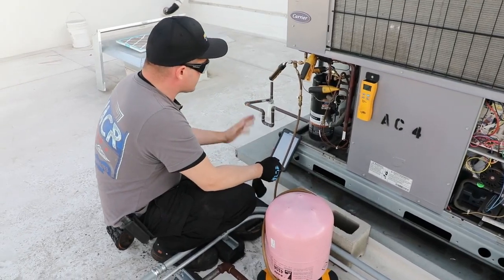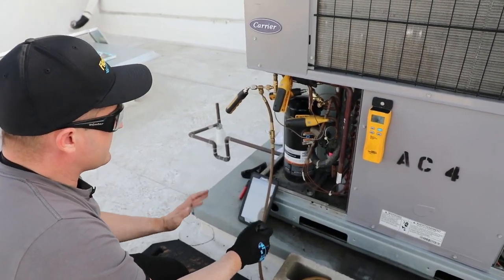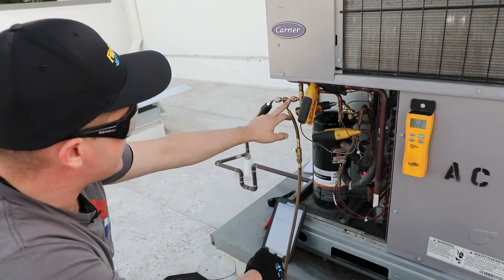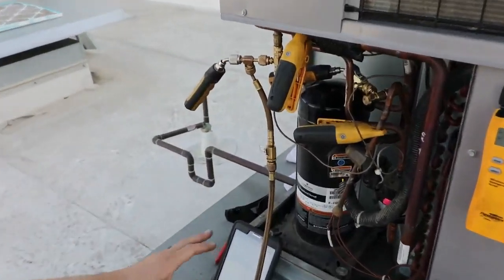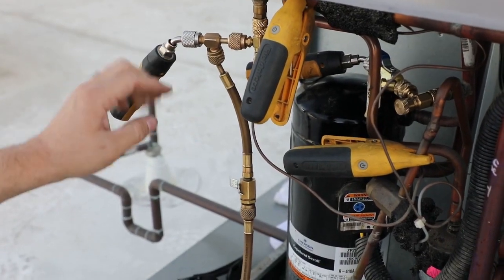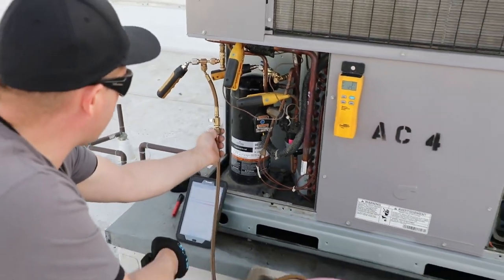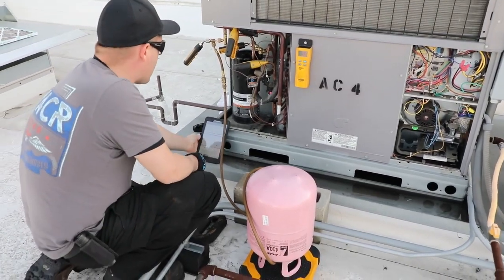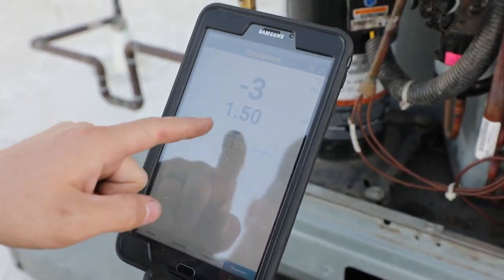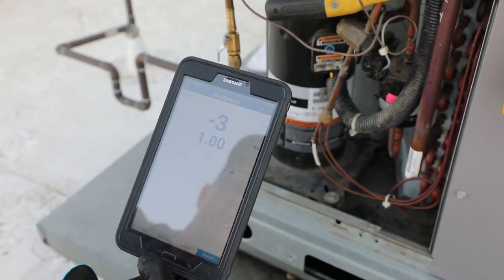This isn't something really recommended by Fieldpiece, but there's nothing wrong with it — it's something really cool you can do with the probes. If you want to go completely without a manifold, you can connect the probes with the charging T and actually charge using the JobLink probes. I've got the high side probe hooked up, the low side probe hooked up, a ball valve right here, and my refrigerant tank hooked up. We've purged the line, and now we can actually add refrigerant with the charging T and continue to see our scale. That's how much refrigerant we've put in the system already, and we can add more and watch the number change as we add refrigerant.